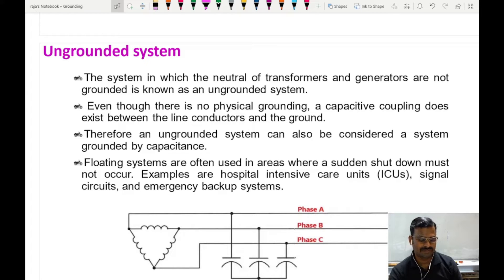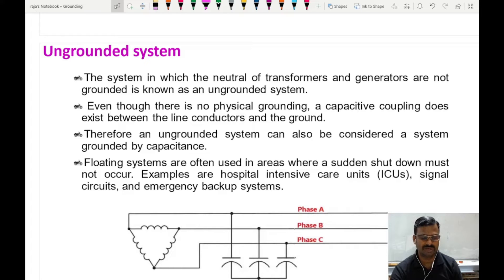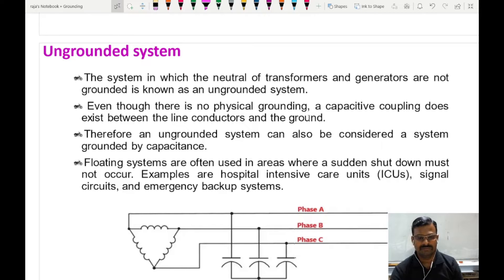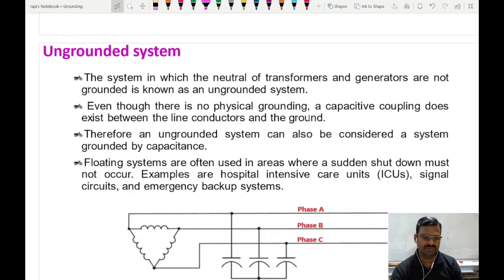There is a lightning strike and there is a surge voltage because of that. If you have system grounding, this surge current will flow through the system grounding to the earth. But this system does not have any ground from the neutral point. So the high voltage induced in the power system because of lightning or switching surges cannot go away from the system. This is a big problem of the ungrounded system.